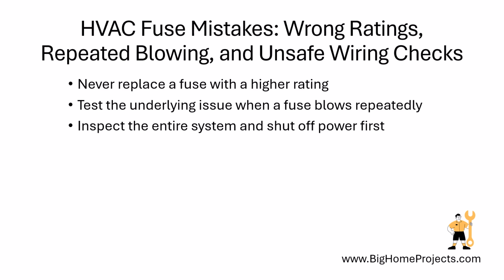If it blows again quickly, stop resetting it and have a qualified technician test the wiring, transformer, motors, and control board. People also sometimes inspect only the indoor unit, while the outdoor condenser, thermostat wiring, and low-voltage cable can cause the failure, so check the entire system and shut off power before touching anything.